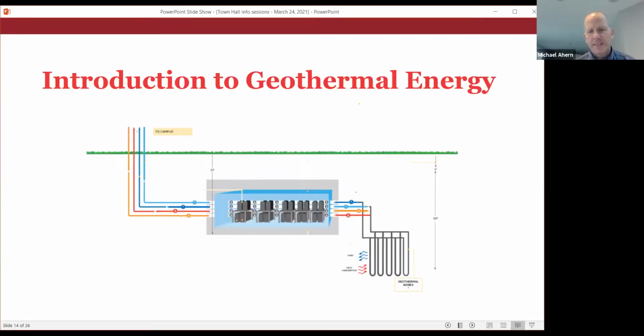A little bit about geothermal: when you go deep enough into the ground, roughly 600 feet down, there's a constant temperature of around 55 degrees. We're leveraging that constant earth temperature to both heat and cool our buildings. In summer, we take that 55-degree water, send it down tubes into the earth, and it comes back up at 55 degrees. Heat recovery chillers bring it down to 42 degrees, which is then delivered to the buildings to keep them cool. In winter, it's the opposite: we get that 55-degree water from the core of the earth and use the heat recovery chillers to boost it up to 130 degrees, which allows us to heat the buildings and provide domestic hot water for showers, kitchens, sinks, and so forth.